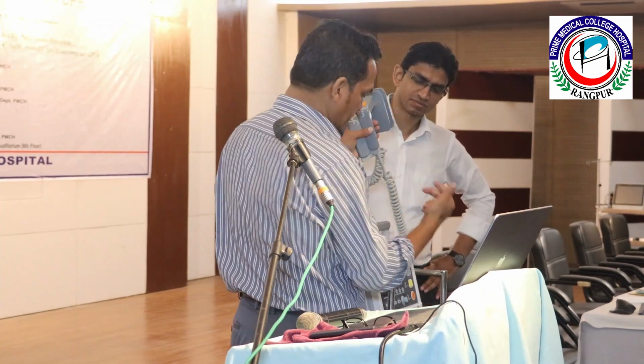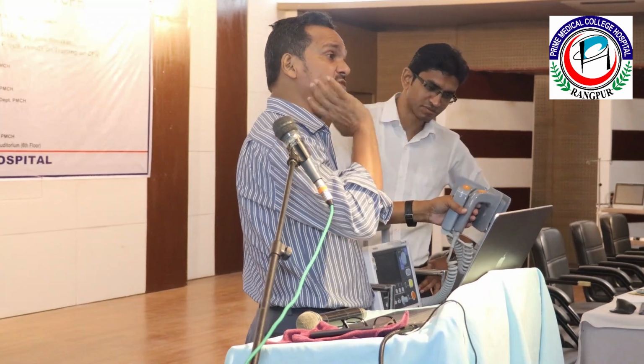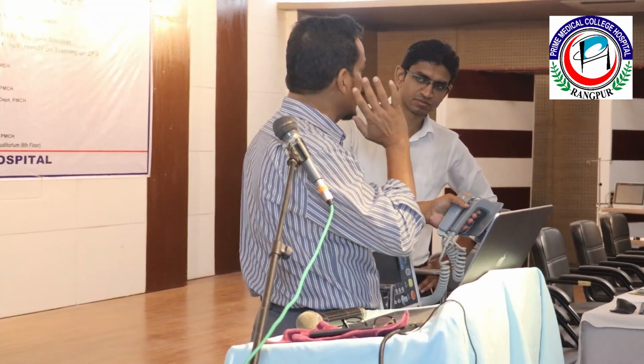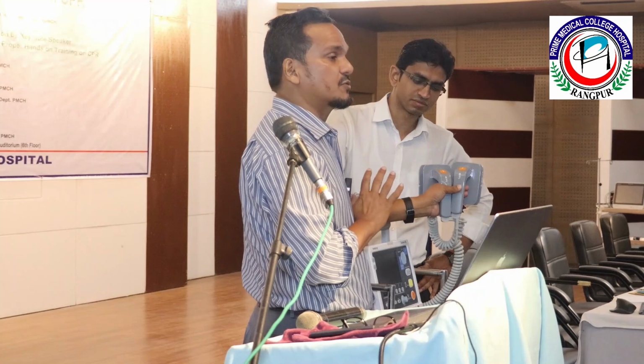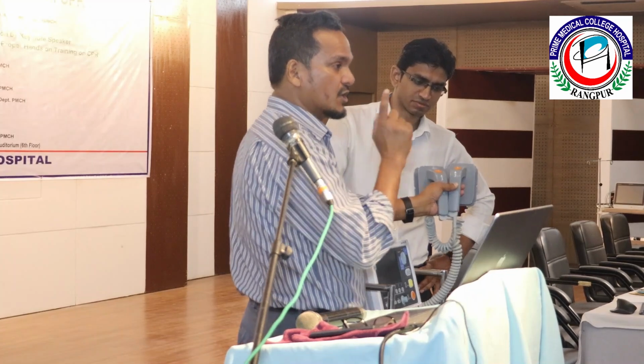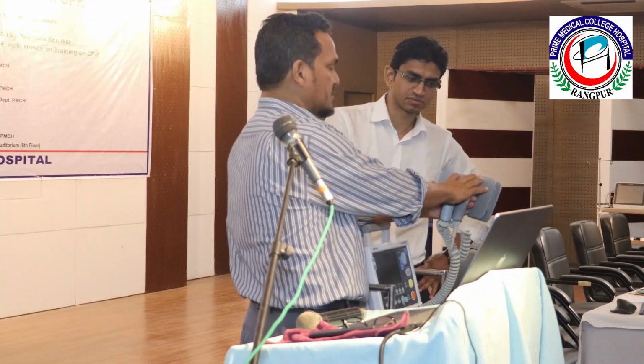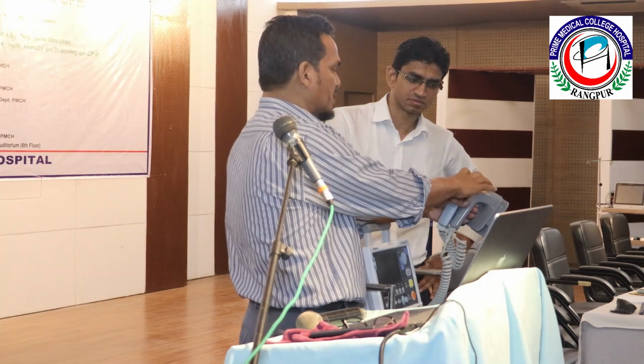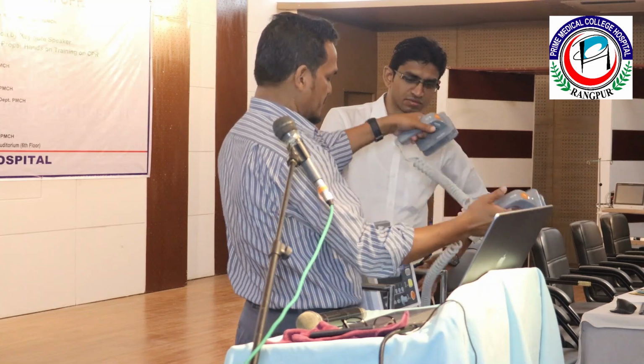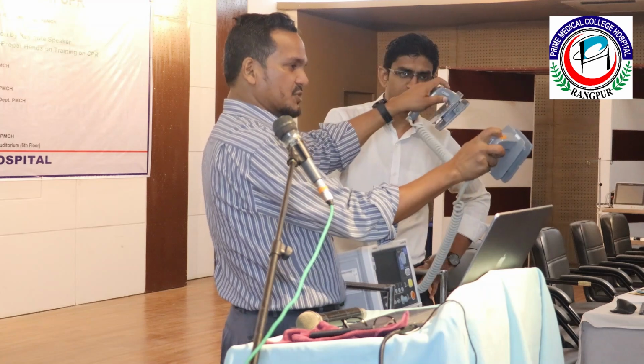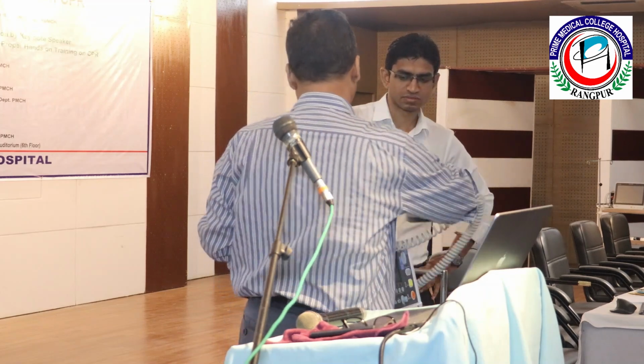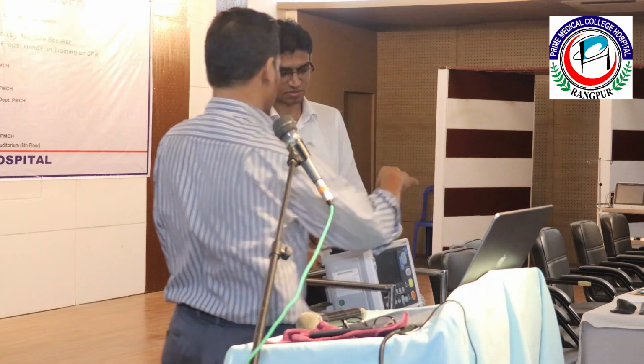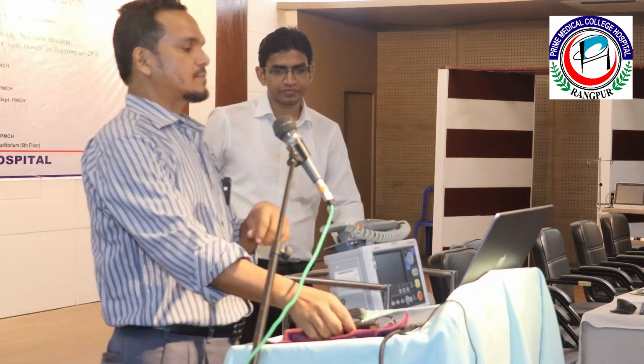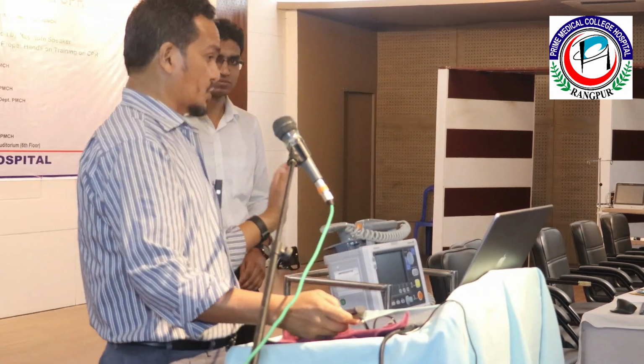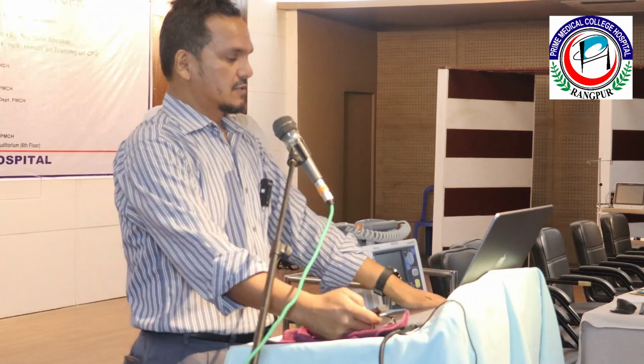Two options. The orange button is the shock delivery button, universal. Each and every machine contains the same color code. Yellow button: charge. Delivery: red or orange button. Just charge it, push it. We'll show it in more detail.